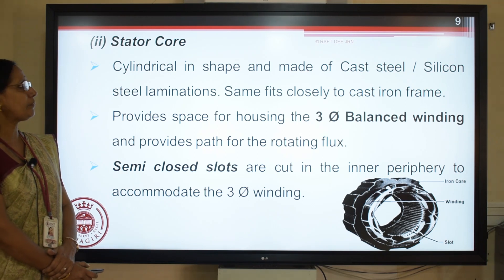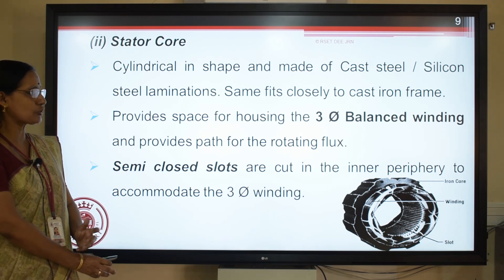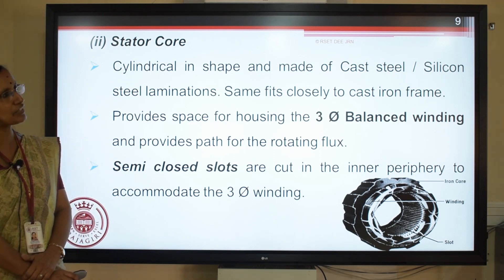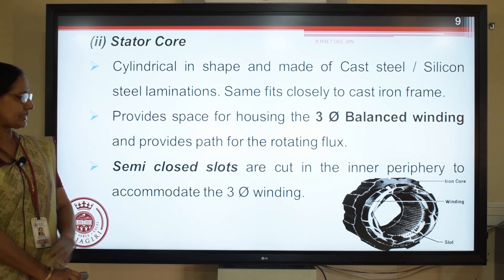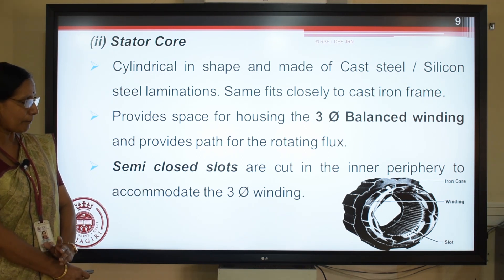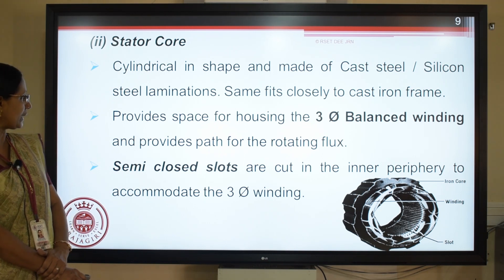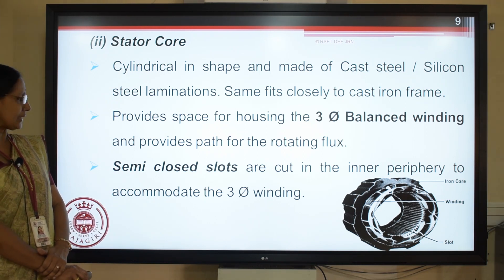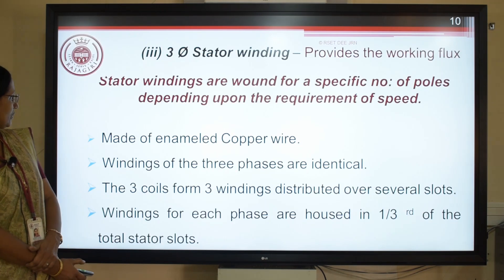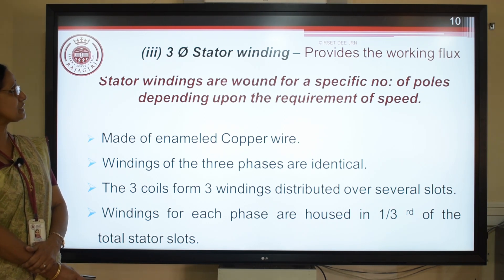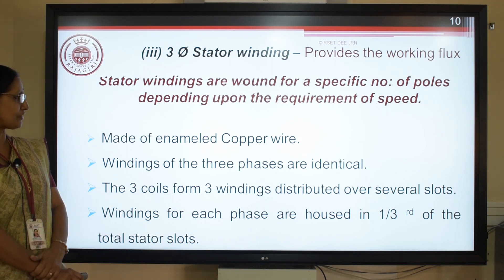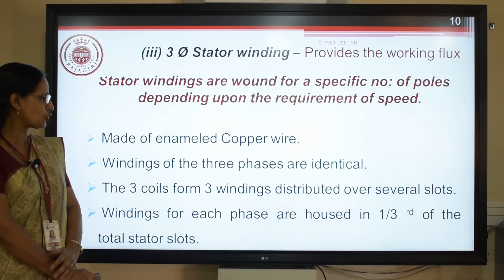The main function of the stator core is to provide the working flux, which is provided by the three-phase winding accommodated in the stator core. It is cylindrical in shape and is accommodated within the frame. Semi-closed slots are cut in the inner periphery to accommodate the three-phase winding. The three-phase winding is made up of enameled copper. Being a three-phase machine, windings of the three phases should be identical.